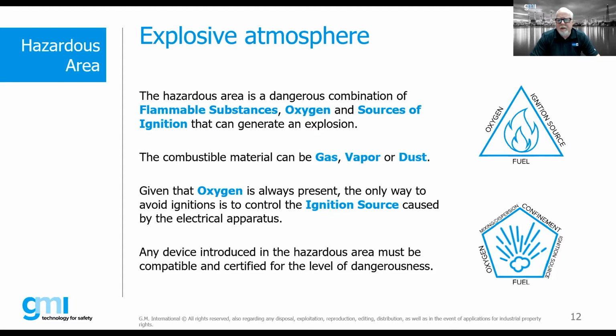What we're really concerned with is the potential ignition source. Within the relevant worldwide standards, there's a whole bunch of different ignition sources that we talk about with regards to electrical and mechanical equipment. What we're really concerned with regarding intrinsically safe is the minimum ignition curve, or the minimum ignition energy, based upon the particular gas or vapor in which we're applying a piece of EX equipment, specifically intrinsically safe. The equipment that we use in these areas must be certified for those particular applications. That gets into an interesting concept that we may talk about a little later with regards to simple devices and non-simple devices and the level of certification required for both.